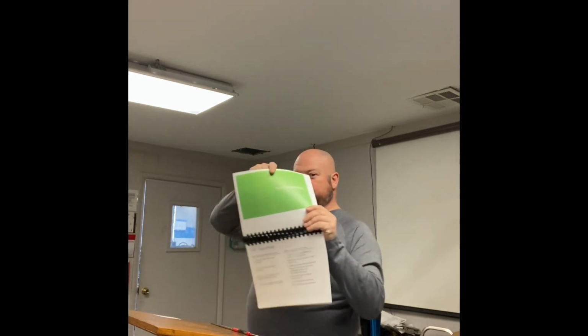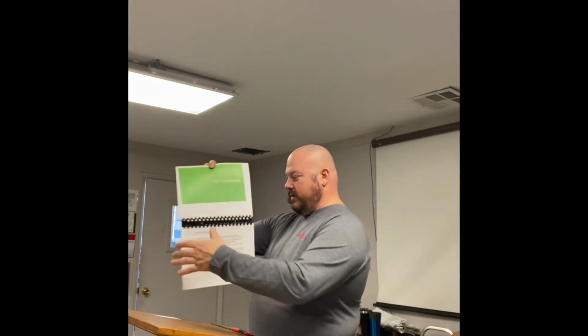Okay, now we're into TXV troubleshooting. Pretty simple to find. This big gigantic green sheet says TXV troubleshooting. Okay? If you're trying to understand, some of them are adjustable, some of them aren't. If you buy a residential comfort cooling expansion valve, most of the time they're not going to be adjustable. If you're buying a refrigeration expansion valve, they most of the time are adjustable. Okay? You need to understand how to adjust it before you start adjusting an adjustable expansion valve.